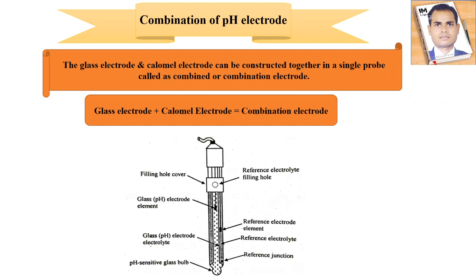You can see the diagram for the combined electrode. Here you will see the filling hole cover, and at the center a reference electrolyte filling hole. At the lower side, there is the glass electrode element for pH, and here is the reference electrode. There is also the reference electrode solution, the pH-sensitive glass bulb, and the reference junction with electrolyte solution. The role of the electrolyte is to conduct current easily — whatever current is given to the electrode will easily pass from one place to another within the system.